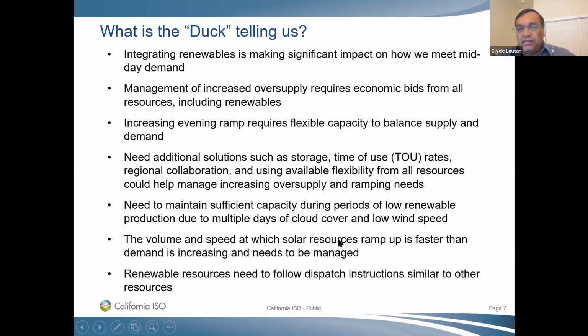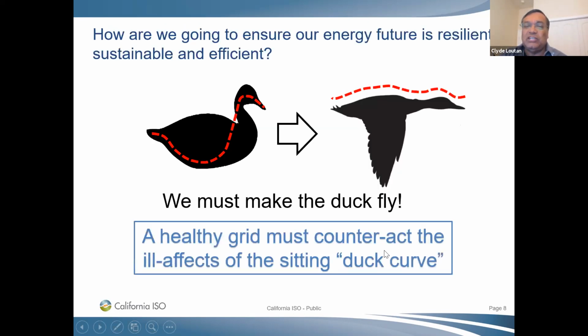And one of the other things too in your system, renewable resources, to help us control the grid, they need to follow dispatch instructions. So if a balancing authority like the ISO gave renewables instructions to either back down or increase production if they have headroom, or if they're not operating at full capacity, they need to be able to follow those dispatch instructions. So essentially, everything we talked about so far is to do one thing here, which is to flatten the belly of this duck.